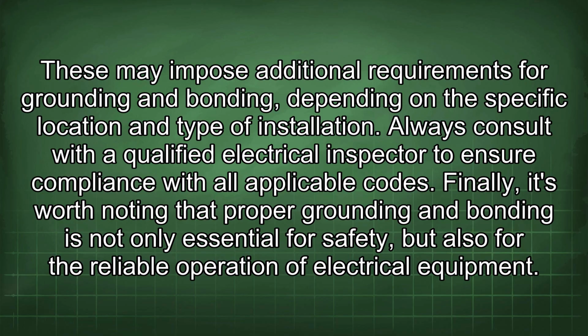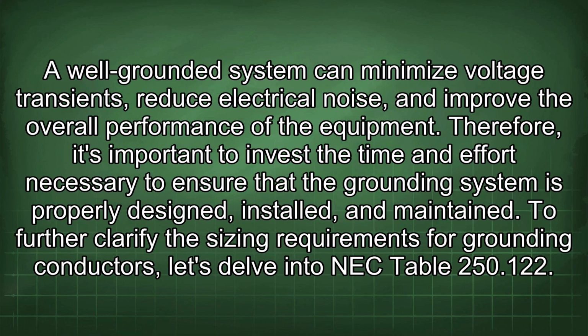These may impose additional requirements for grounding and bonding, depending on the specific location and type of installation. Always consult with a qualified electrical inspector to ensure compliance with all applicable codes. Finally, it's worth noting that proper grounding and bonding is not only essential for safety, but also for the reliable operation of electrical equipment.